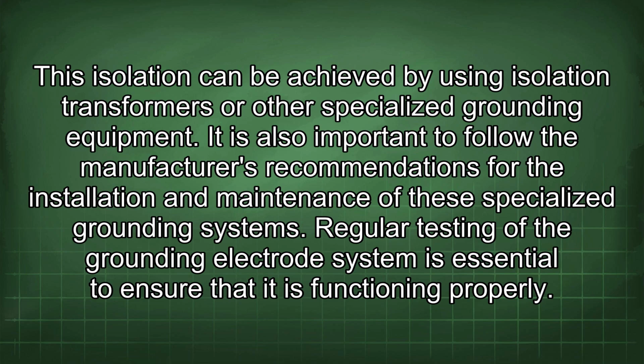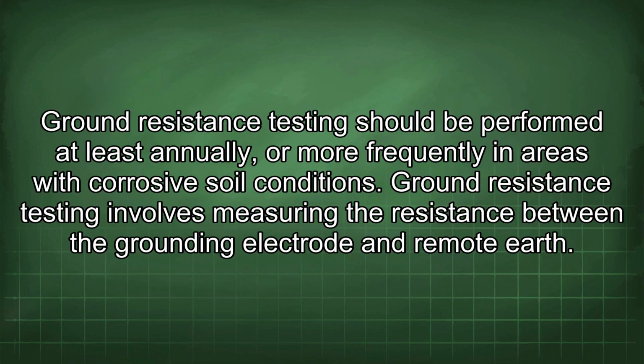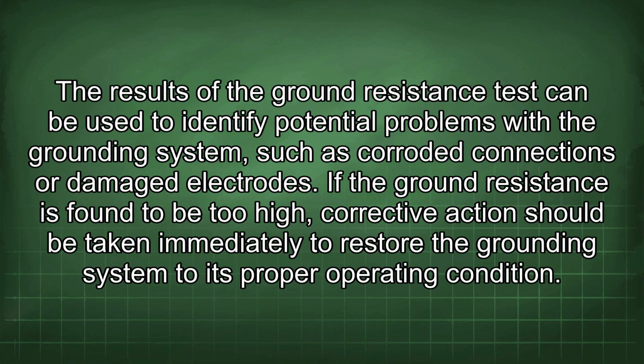Regular testing of the grounding electrode system is essential to ensure that it is functioning properly. Ground resistance testing should be performed at least annually or more frequently in areas with corrosive soil conditions. Ground resistance testing involves measuring the resistance between the grounding electrode and remote earth. The results of the ground resistance test can be used to identify potential problems with the grounding system, such as corroded connections or damaged electrodes. If the ground resistance is found to be too high, corrective action should be taken immediately to restore the grounding system to its proper operating condition.